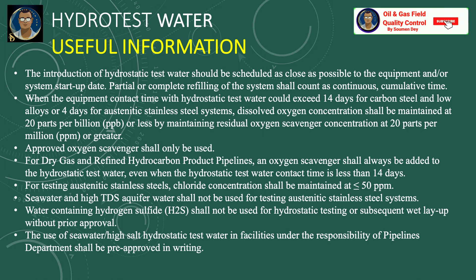Some useful information about hydrotest water selection: the introduction of hydrotest water should be scheduled as close as possible to the equipment and/or system startup date. Partial or complete refilling of the system shall count as continuous cumulative time. When equipment contact time with hydrotest water exceeds 14 days for carbon steel and low alloys, and 4 days for austenitic stainless steel systems, dissolved oxygen concentration shall be maintained at 20 ppb or less by maintaining residual oxygen scavenger concentration at 20 ppm or greater. Approved oxygen scavengers shall be used.